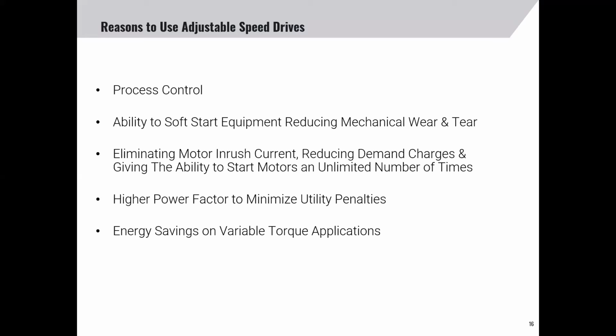Another reason to use an adjustable speed drive is eliminating motor inrush. Again, it gets back to starting versus accelerating the motor. As I just explained, with an adjustable speed drive, you program the drive to accelerate up to full speed, but you start at 0 frequency and 0 voltage, and then you control the amount of inrush that the motor sees, which reduces the demand charges. And this is very important in very large horsepower motors. So for example, if you're starting a 500 horsepower, 800 horsepower, 1,000 horsepower motor, if you can eliminate the motor inrush, you'll certainly have the ability to reduce potential demand charges that would be imposed by the utility.